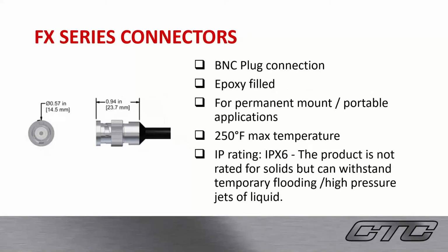Here's our FX series connectors. This is our BNC plug connection, which is epoxy filled, and this is for permanent mount and portable mount applications. It has a 250-degree Fahrenheit max temperature, and the IP rating for this is IPX6, which is, again, the product is not rated for solids, but can withstand temporary flooding and high-pressure jets of liquid.